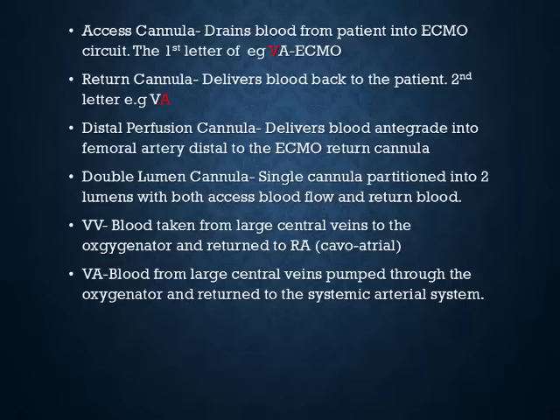The first thing is to know the definitions routinely used in the literature. The access cannula is the cannula that drains blood from the patient into the ECMO circuit — by convention, that's the first letter. So when you see VA or VV, the first letter is the access, which is venous. The return cannula delivers blood back to the patient and is by convention the second letter. The distal perfusion cannula delivers blood into the femoral artery, distal to the ECMO return cannula, so you don't lose perfusion to the lower limbs. There's also a double lumen cannula — a single cannula partitioned into two lumens with both access and return functions.